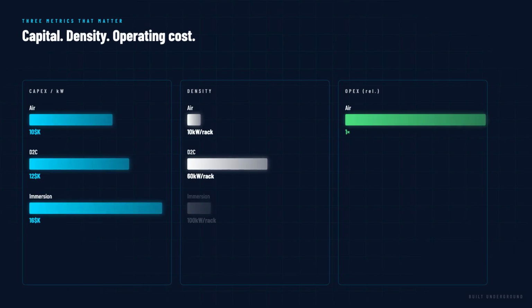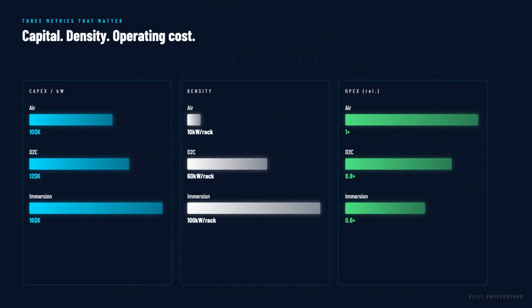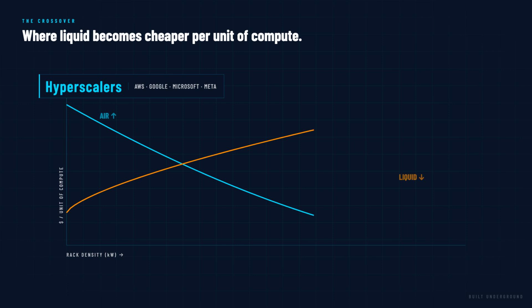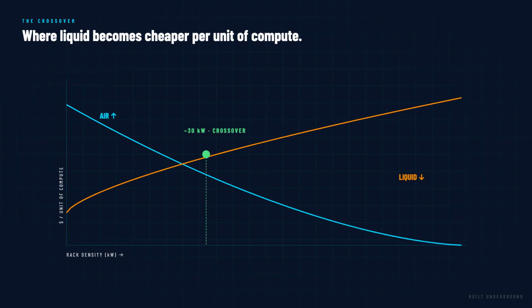The critical insight is this: the cost per kilowatt of capacity goes up with liquid cooling, but the cost per kilowatt of actual compute delivered goes down because you eliminate thermal throttling, reduce fan power, and pack far more processing into the same building footprint. For hyperscalers building AI training clusters, the maths is simple. A building that fits twice as many GPUs per square meter, running at full speed without thermal throttling, pays for the cooling premium many times over.